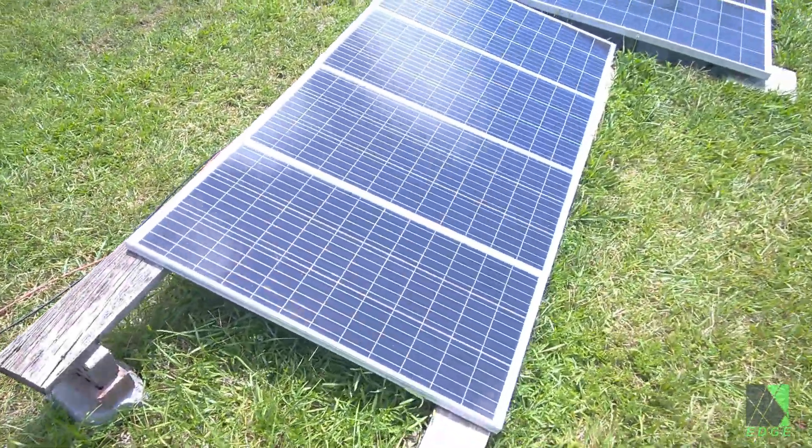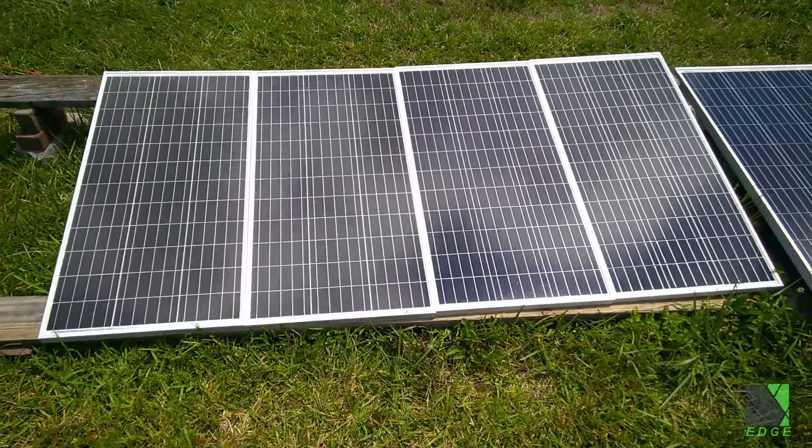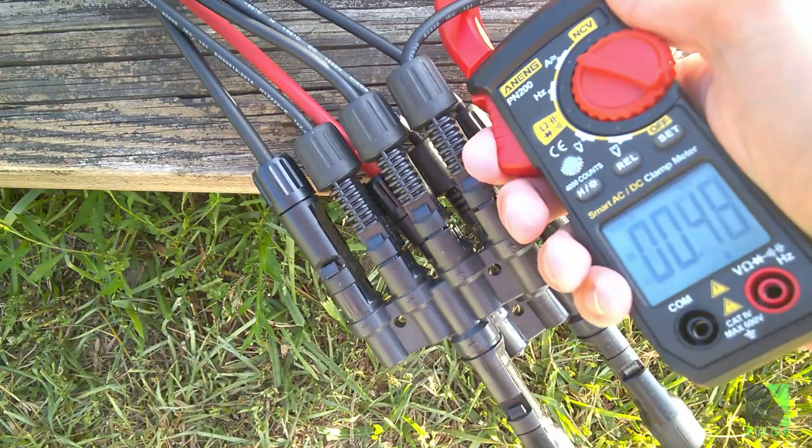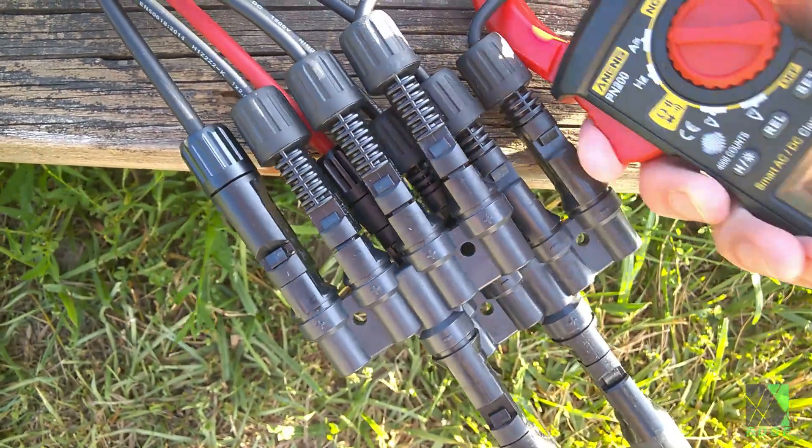You cannot tell by looking at a string of solar panels how much current each panel is producing, but the knowledge is quickly gained by simply clamping each wire from each solar panel individually and notating how much current is flowing through.